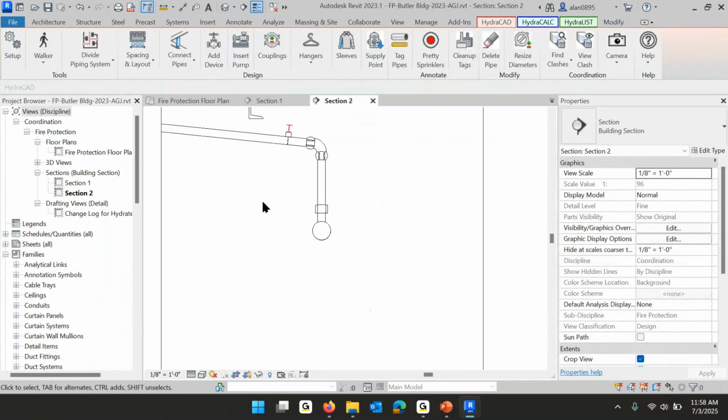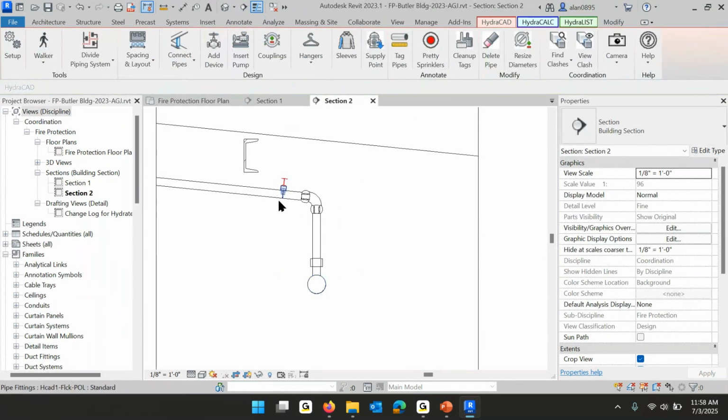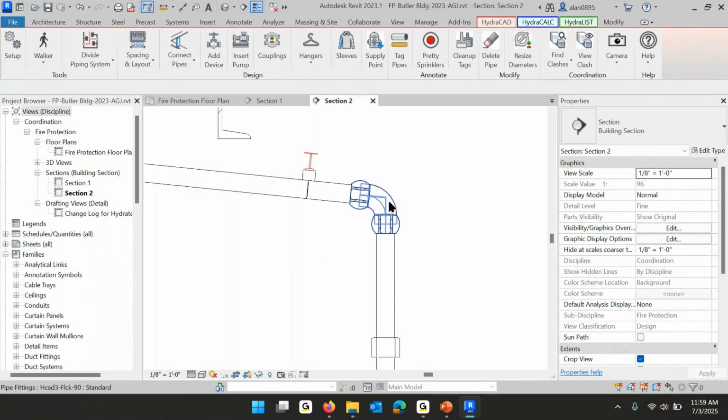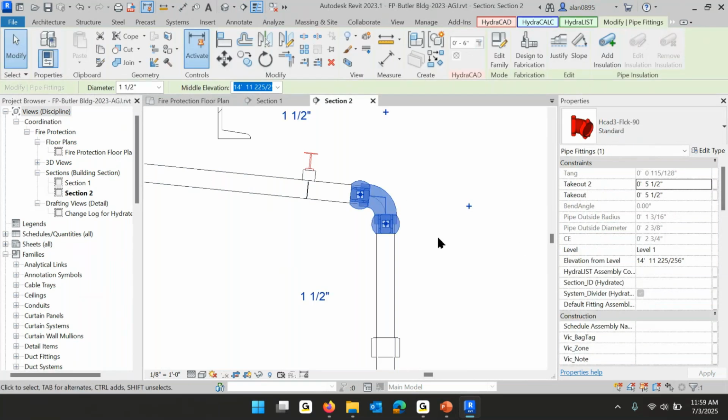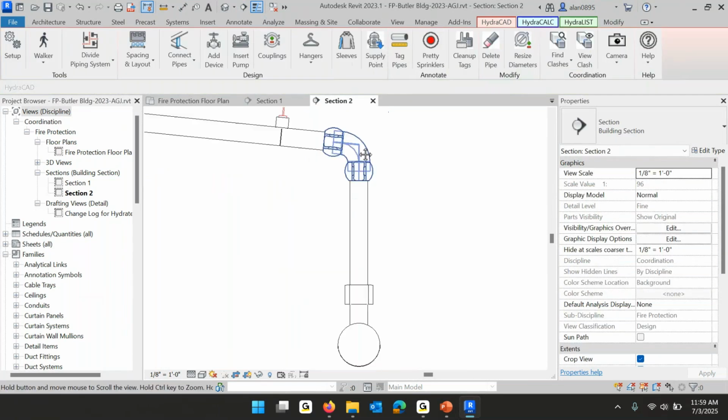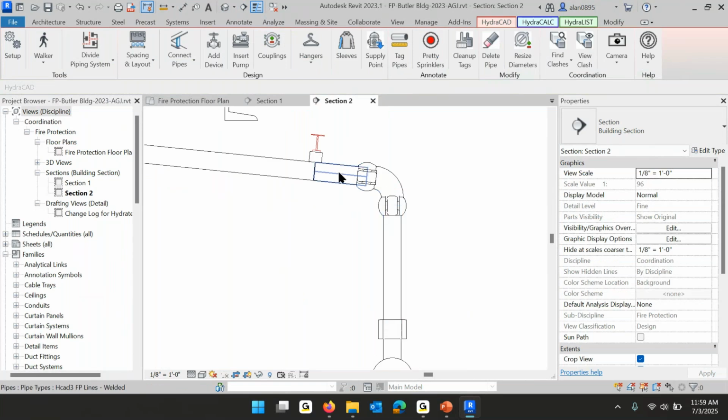Revit said, oh, here's a low pipe, here's a high pipe. You're tying that high pipe into the low pipe. I'll go draw straight down into it. So this is a 94-degree elbow or something. It's not a 90-degree elbow. And if it's a firelock elbow, you will not be able to make that up.